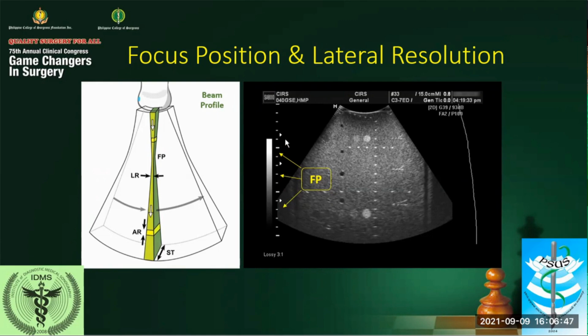So the focal position can be selected. Some machines will have multiple focal points, some will have one only. But the point is the focus may be adjusted. The position of the focus may be adjusted. It can be set to the near field or it can be set to the far field.